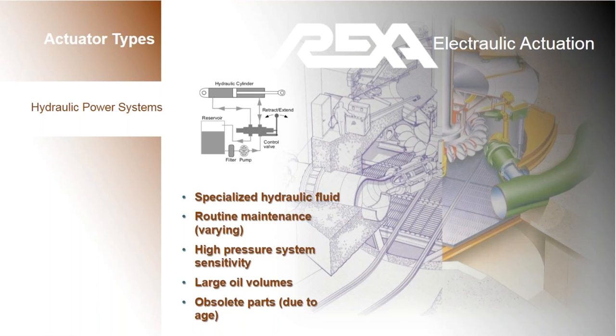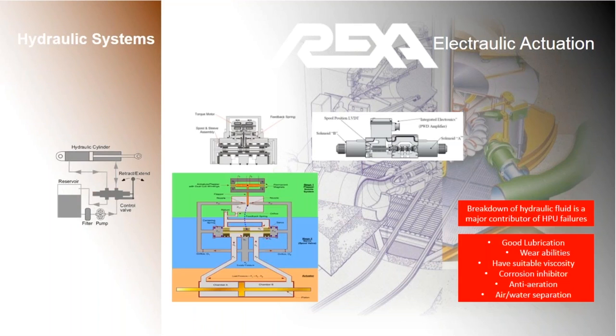Although there are many benefits, they are not immune to the common problems associated with hydraulic systems. Failures often originate when the fluid's quality in a hydraulic system is compromised. In order to combat the effects of the hydraulic fluid breaking down, hydraulic power units, or HPUs for short, are designed around keeping the fluid clean. Systems that operate at higher pressures or have air over oil run an even greater risk because they are more sensitive to the changing characteristics of the hydraulic fluid.